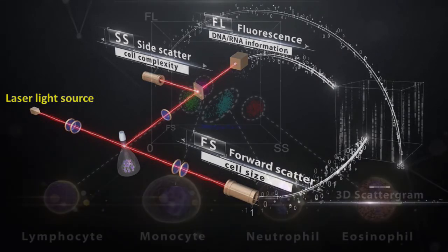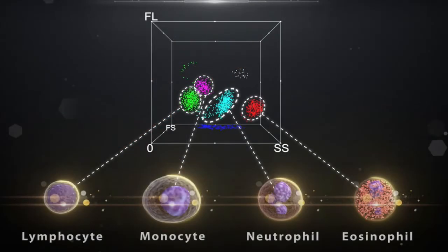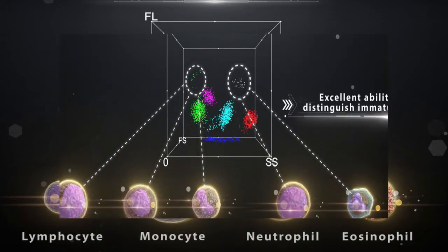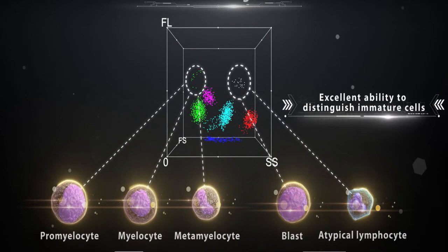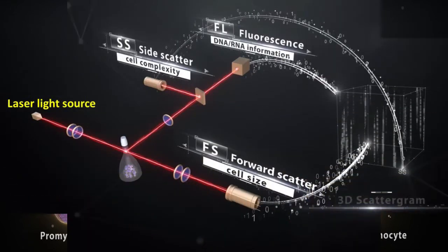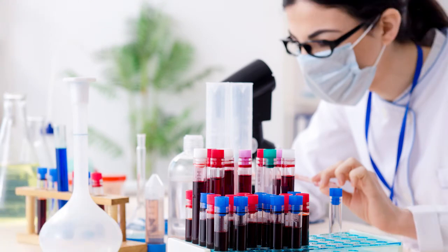All WBC cells are plotted based on their cell size, granularity, and nuclear materials. Immature granulocytes such as promyelocytes, myelocytes, and metamyelocytes, as well as high fluorescent cell populations such as blast cells and atypical lymphocytes, are also plotted in this scattergram. The 3D scattergrams, generated with cellular information including size, complexity, and DNA/RNA data, help clinical experts identify and differentiate cell populations — particularly abnormal clusters undetected by other technologies.